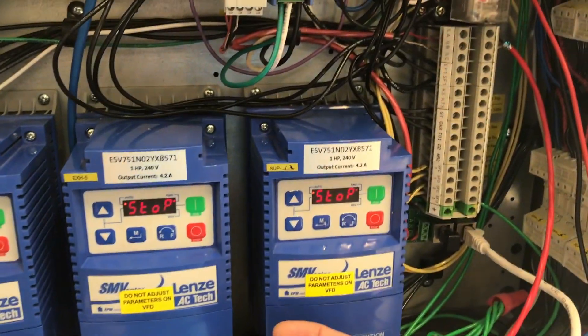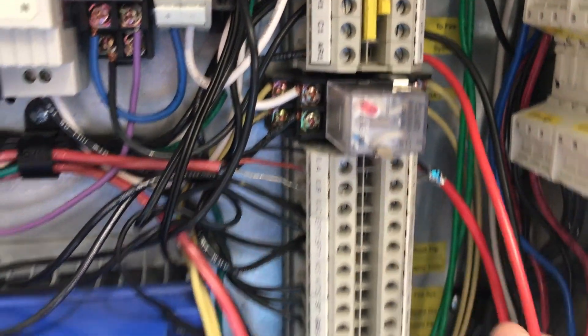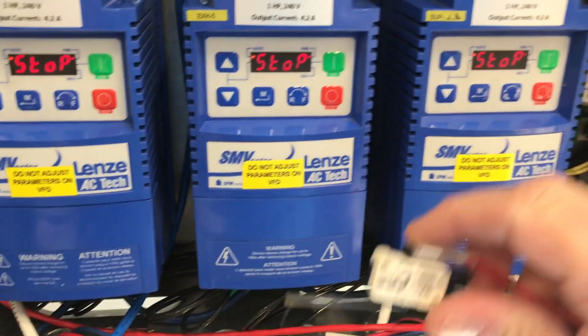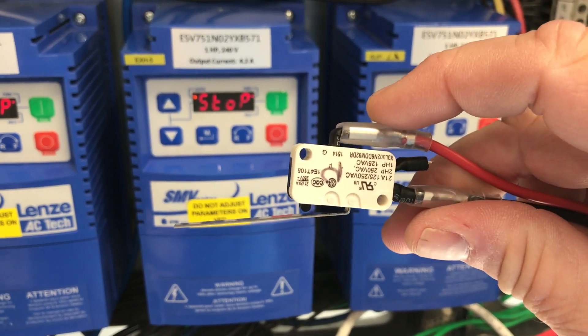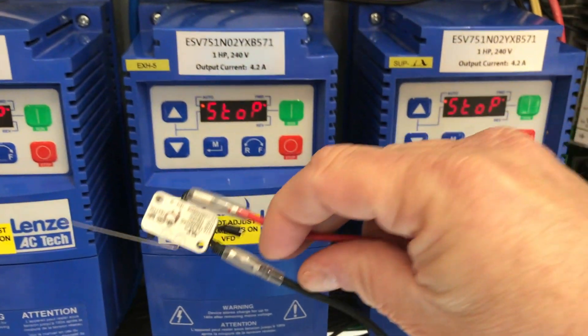This wiring configuration will make the hood package operate normally until the Ansul system is triggered, which will in turn operate the microswitch. Operating the switch will open the C1/AR1 circuit and put the control package into fire mode.